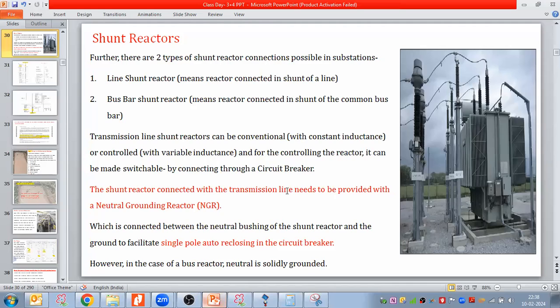Now, the next important concept: whenever the shunt reactor is connected with the transmission line, in shunt of the transmission line, not on the bus bar, that reactor must have a neutral grounding reactor, NGR.